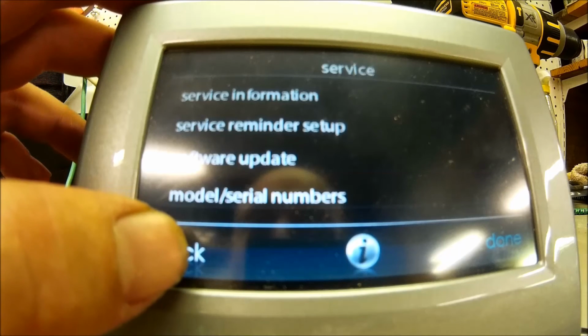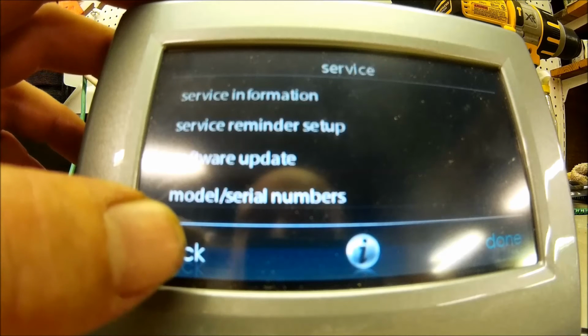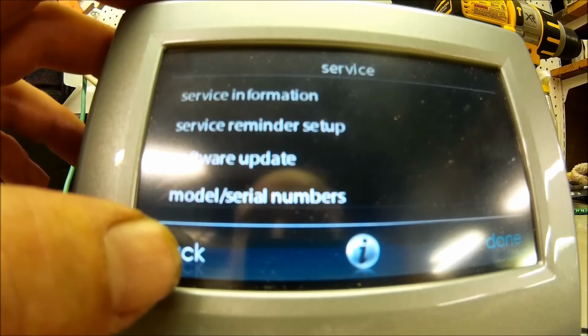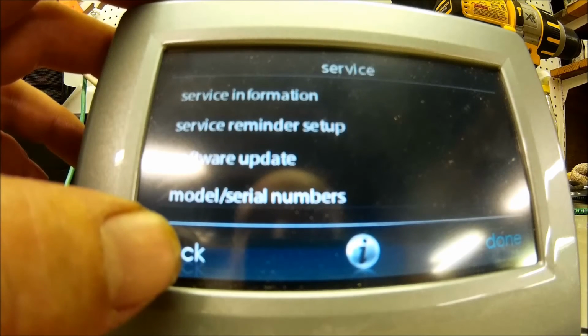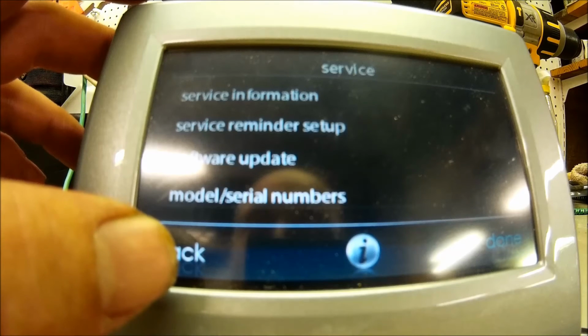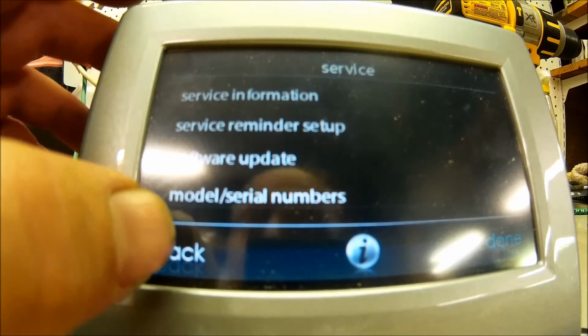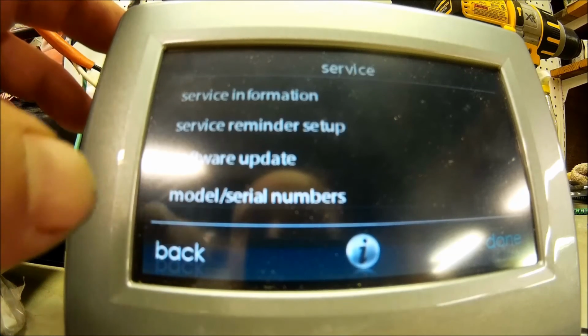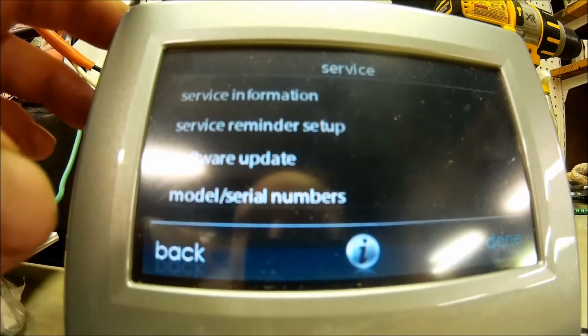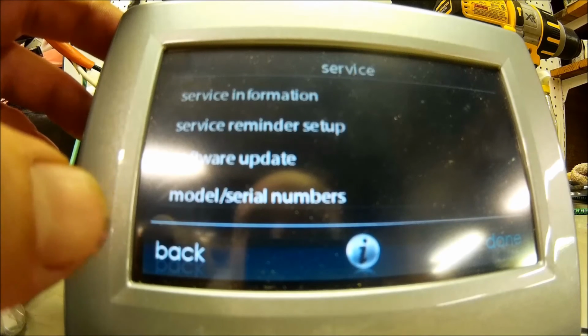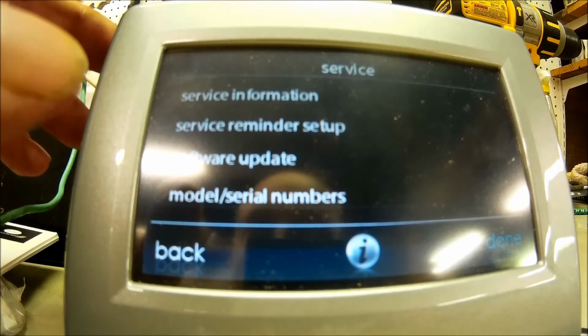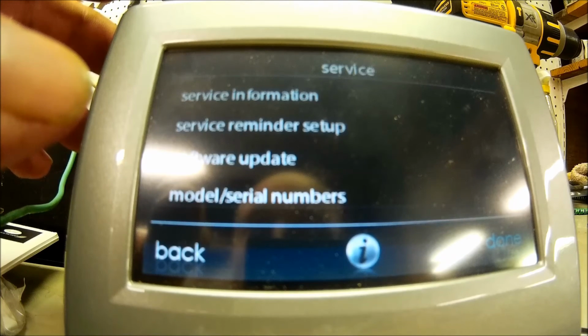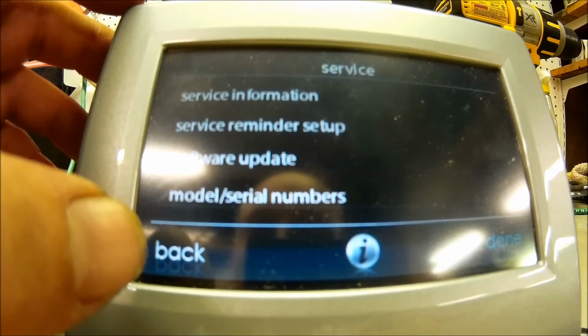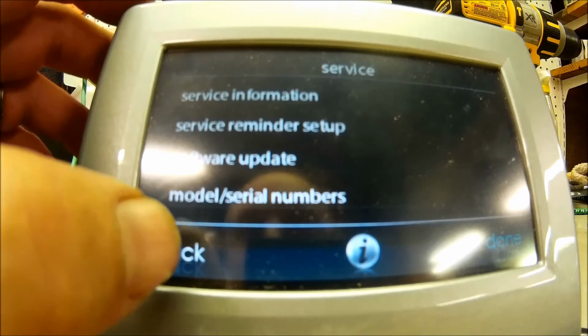One thing with the Infinity Touch or the Infinity Wi-Fi, well, with Infinity Touch, with the software update, the newer equipment, like the 24 and the 25 VNAs, will only work on software version 11 and up. Carrier's on software version 12. I think 13 has come out, but I haven't got the information on it yet. So say you have an older Infinity system installed 3 years ago, and they didn't install the heat pump, but now they installed a 25 or 24 VNA Carrier straight air heat pump. Those units will not work on anything less than version 11 software. Keep that in mind.